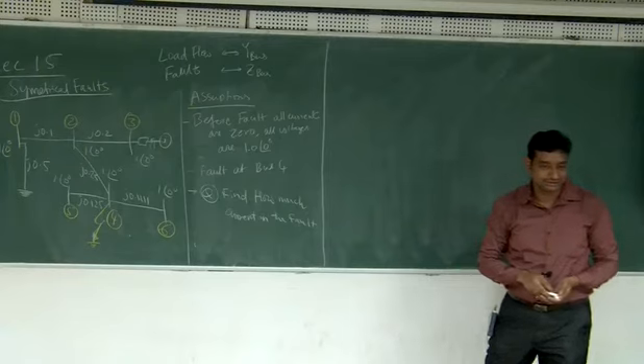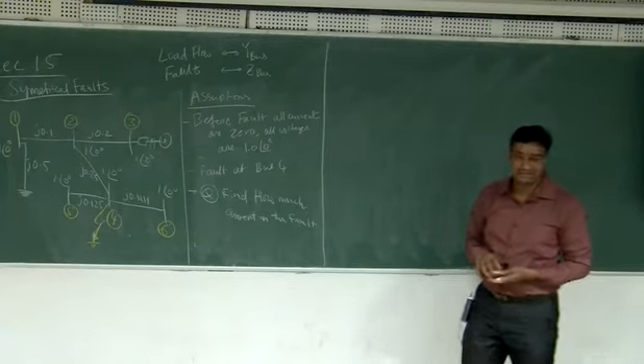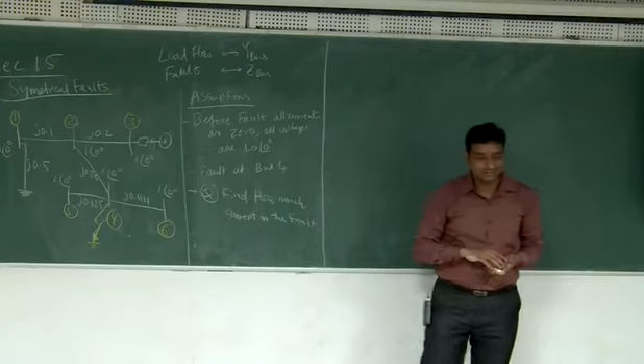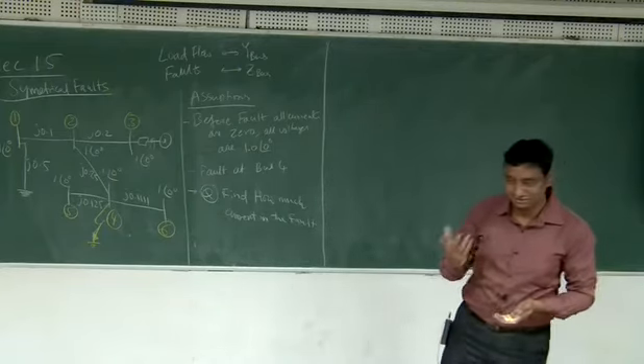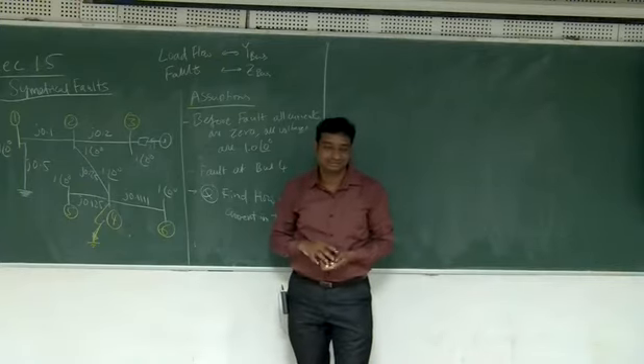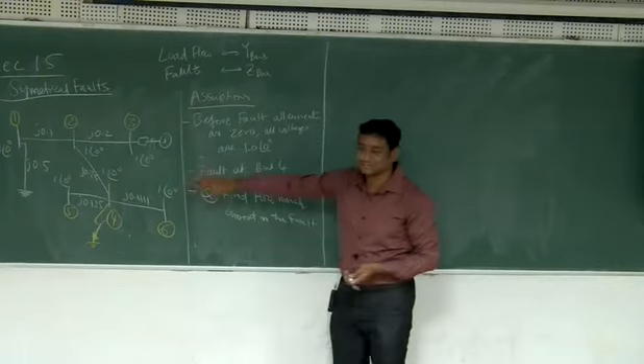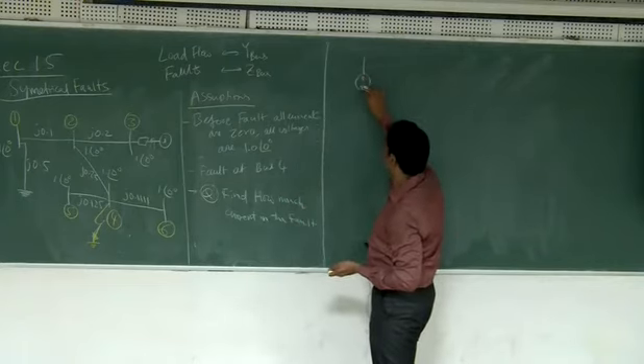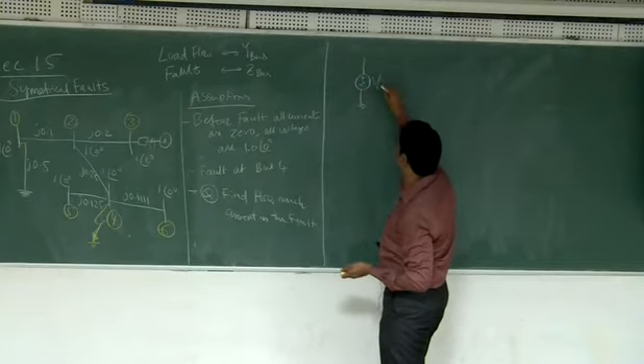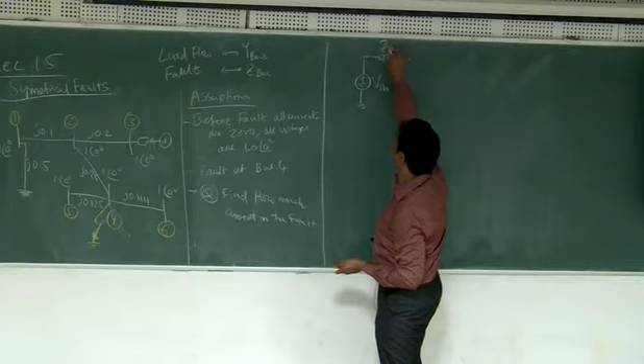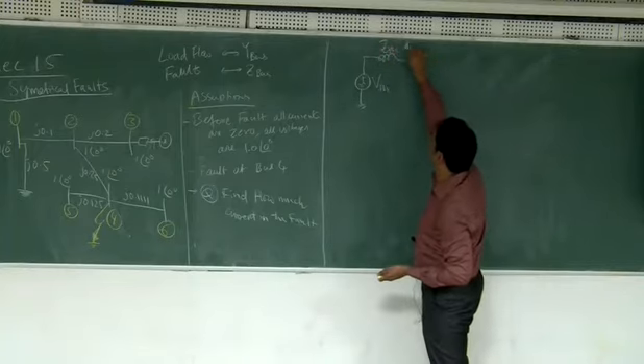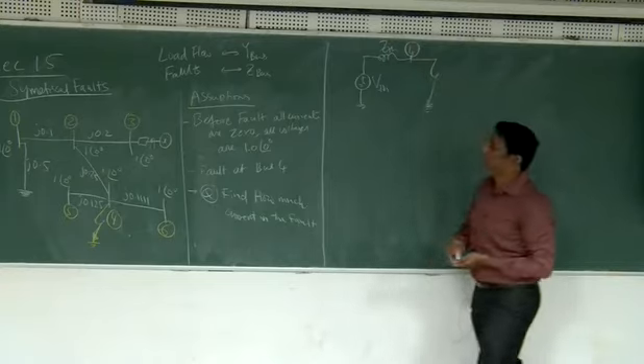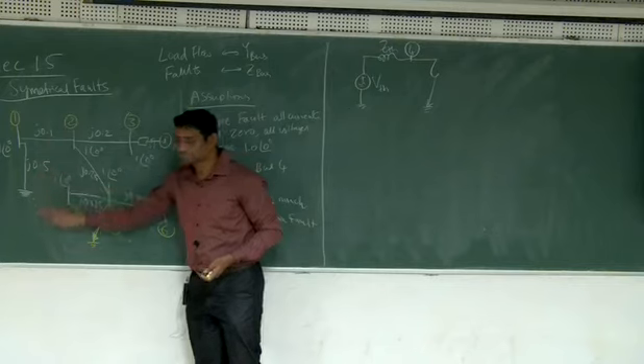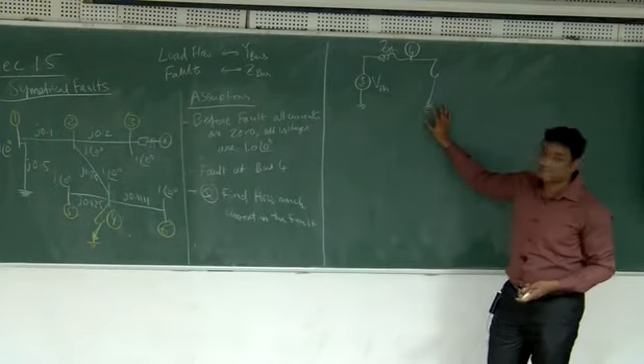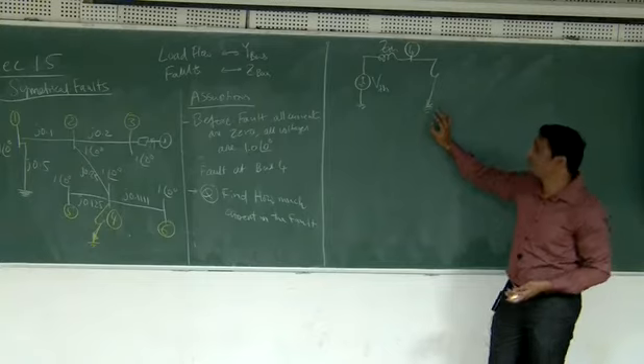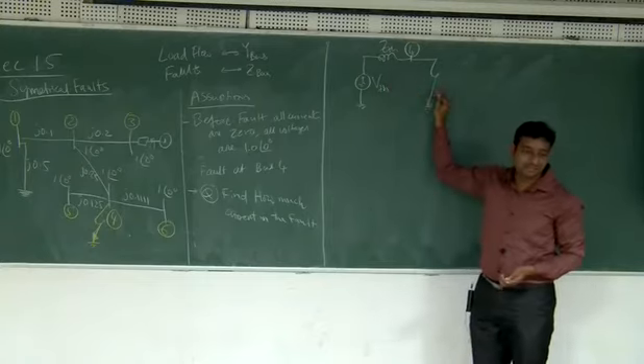Think about your regular circuit calculation. So what will you do? The hint that I want to give you is think about Thevenin's theorem or Thevenin's network theorem and all. So what is Thevenin's network theorem? You can replace the entire circuit with one value of voltage, so let's say VTH, and one value of impedance ZTH, and then this will be your bus 4. Okay, and then this is our fault. So I want to replace this entire network with just this one, and then I can calculate how much is the fault current. So how much is the fault current here? This divided by this, because there is no impedance in the fault.